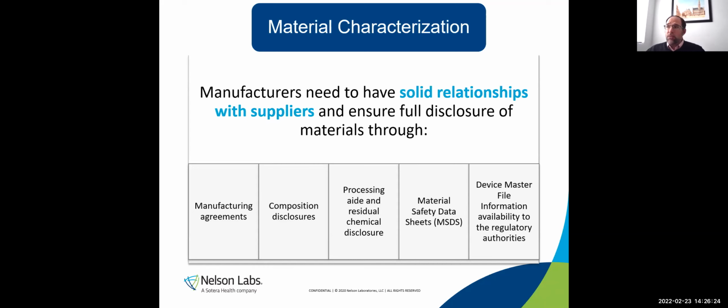There are device master files that companies do. I always say NuSil here. I'm not paid by NuSil. I'm not a spokesperson of NuSil, but they do a great job on their silicone. They have master files with the FDA on a lot of their med grade silicone. And a lot of those master files are testing that's done on different sterilization endpoints. So they'll do testing on irradiated material, on EO material. Now the FDA won't give that to you. You have to contact NuSil to get permission and get it from them. But if NuSil will give it to you, you can now feel more confident, you have good data to help support the change of that material.